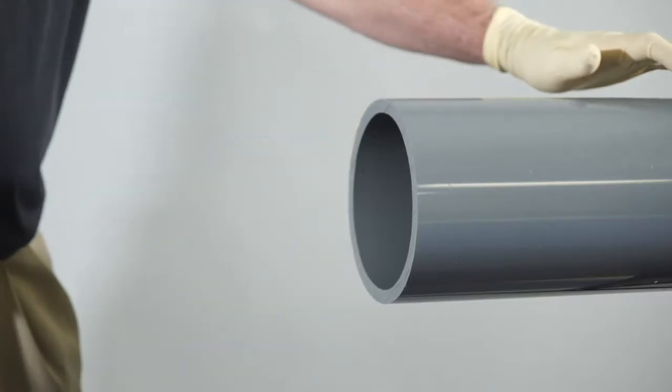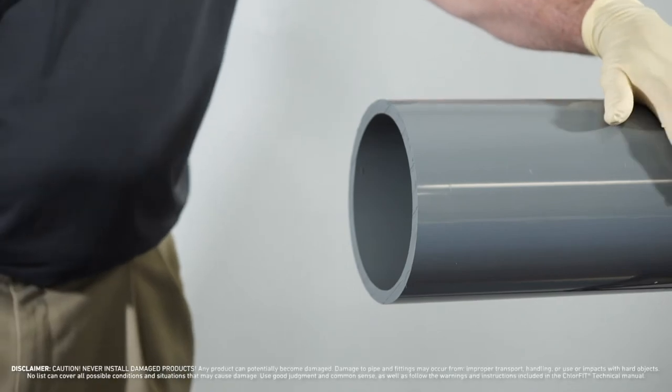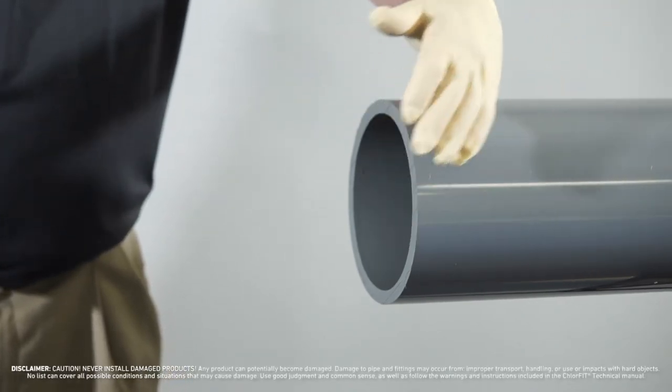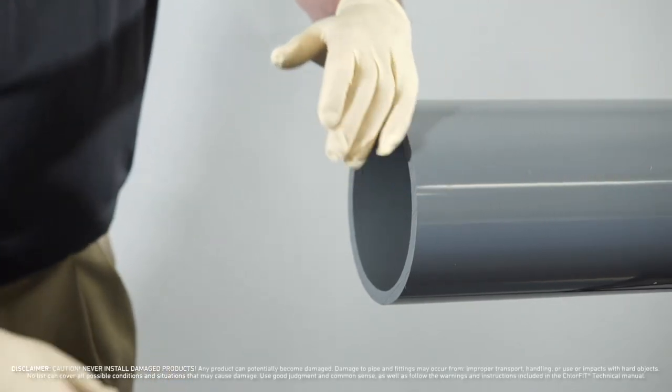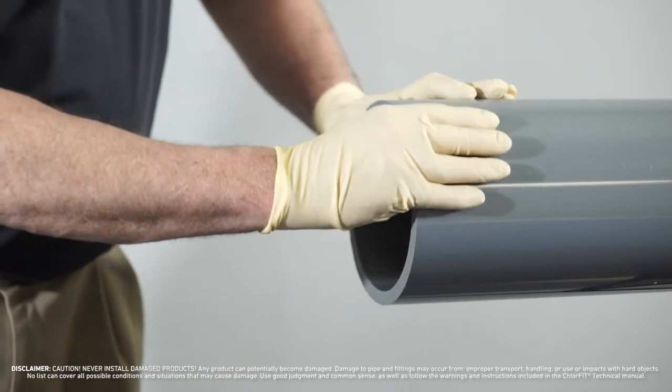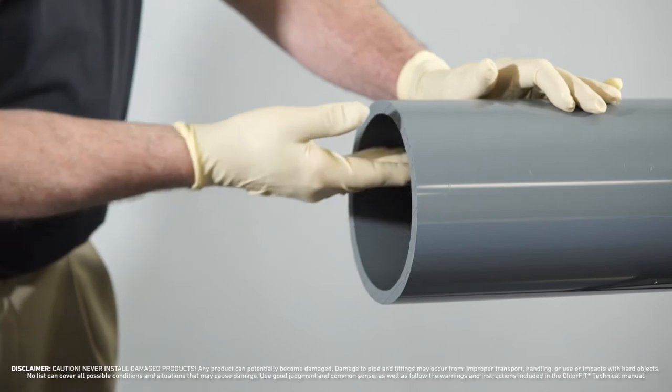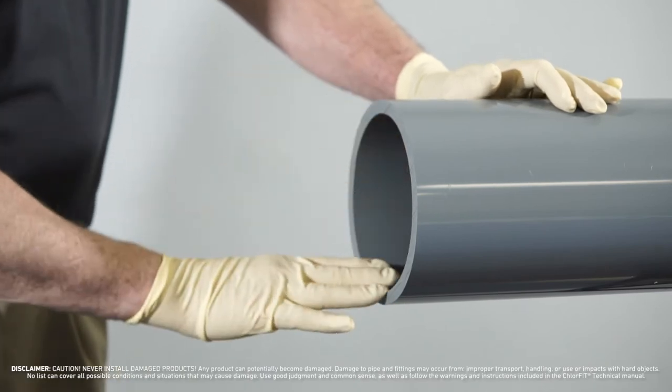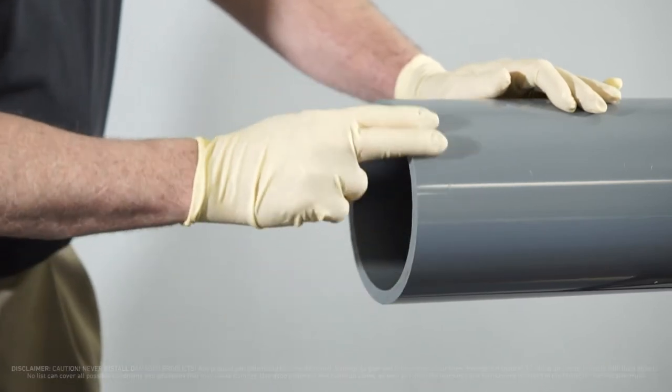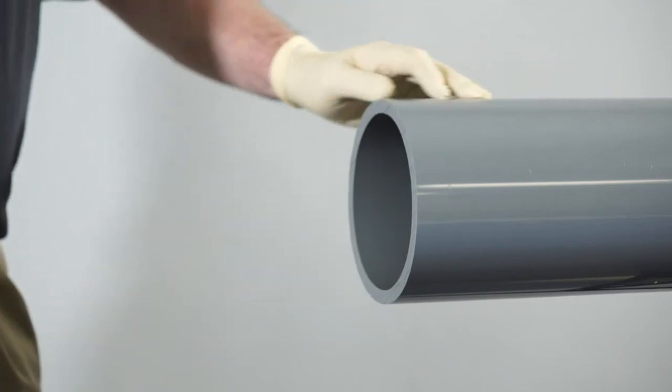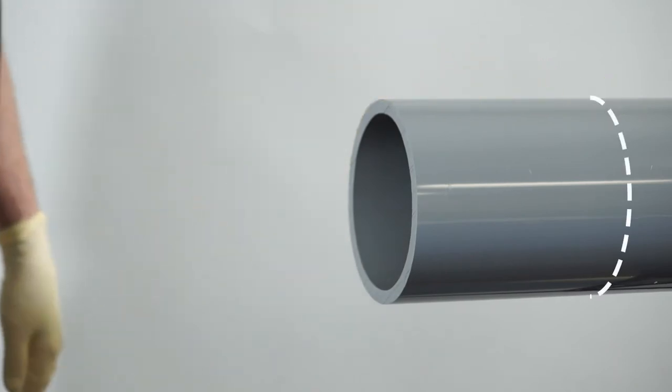Before installation, carefully inspect each length of pipe and fittings for damage. Run your fingertips around the pipe, feeling and looking closely for nicks, cracks, splits, dents, or other marks that could indicate the pipe has been damaged. If the pipe or fitting is damaged, discard the damaged product or cut off six inches of pipe beyond the cracked area.